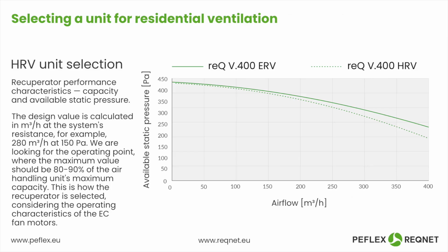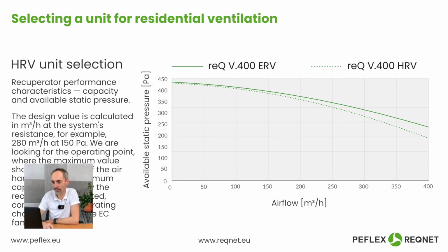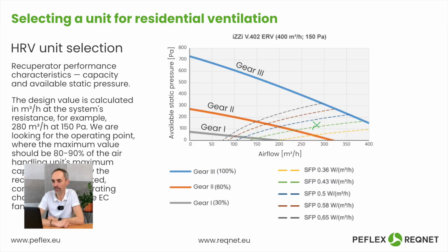We need to select the operating point, meaning this operating point should be the result of the intersection of these two parameters, that is, the available pressure and the airflow rate. Ideally, this operating point should definitely be below the fan's limit curve, and optimally for our installation, it would be best if this operating point is around 80 to 90% of the maximum capacity. And just like, for example, on the capacity curves of recuperators, whether it's reQ or iZZi, that's how we can properly look for this operating point, meaning the recuperator that will meet the requirements of our installation.